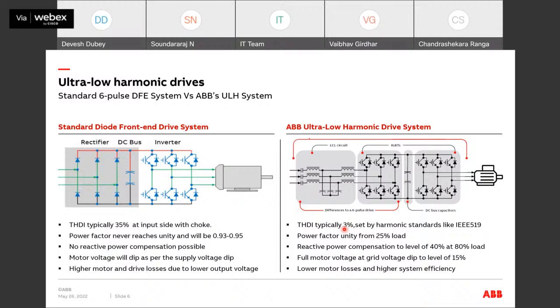Power factor in the diode front-end drives can be in the range of 0.90 to 0.95. While using active front-end drives, you have unity power factor, and that also starting from 25% of load. There is also a possibility that we can have reactive power compensation from the low harmonic drives. Low harmonic drives or active front-end drives have a voltage boost function built into them, so even with a voltage dip, they can still maintain the voltage output to the motor. It will have lower motor losses and higher system efficiency.